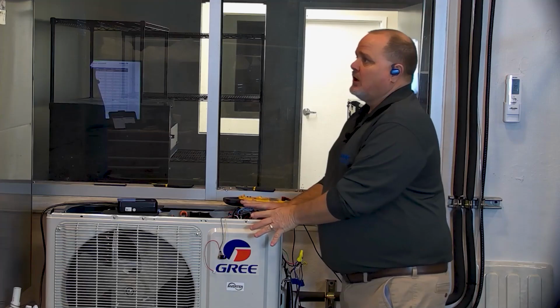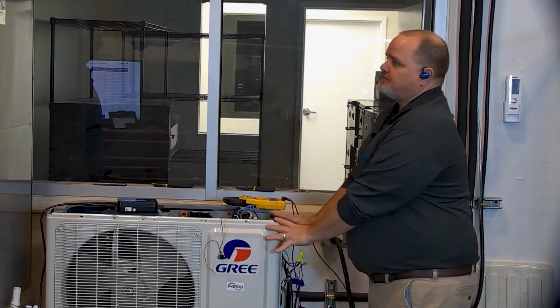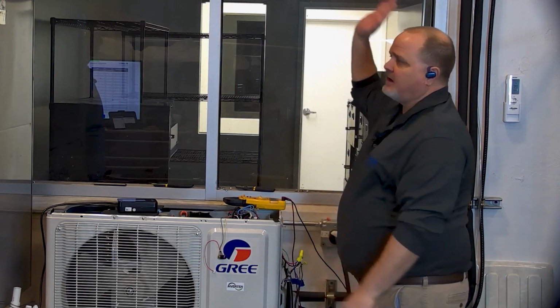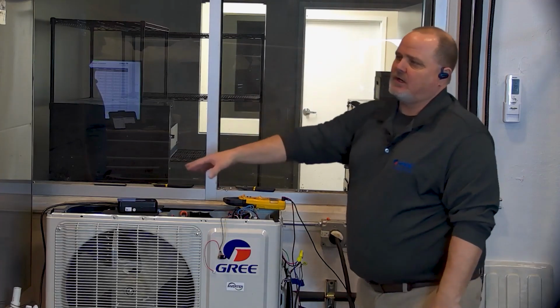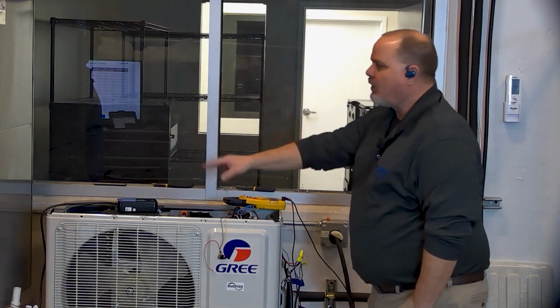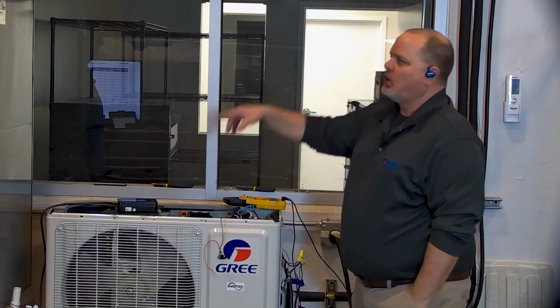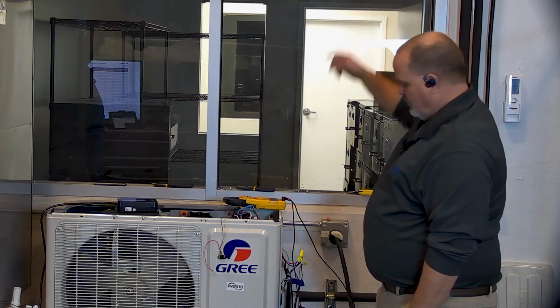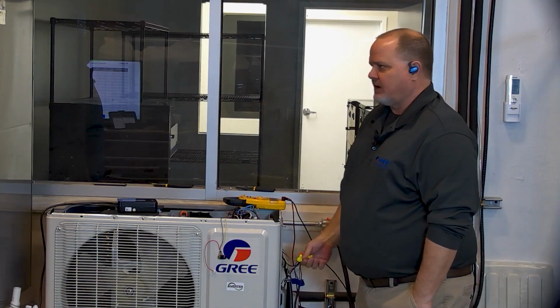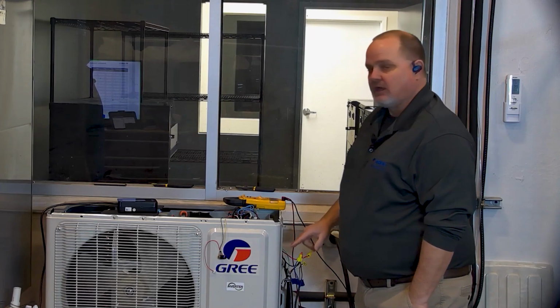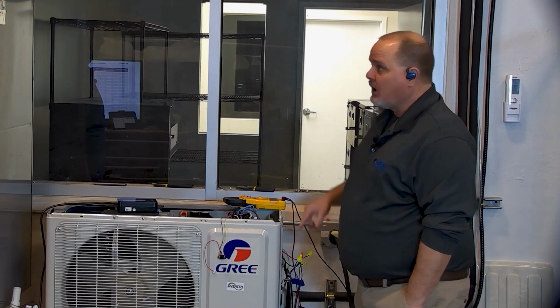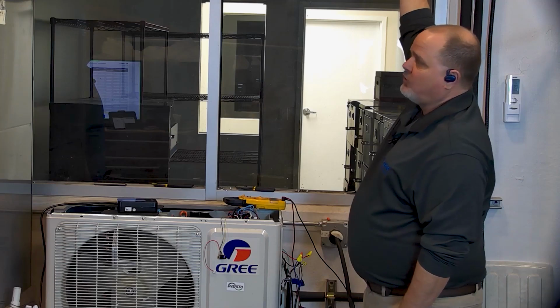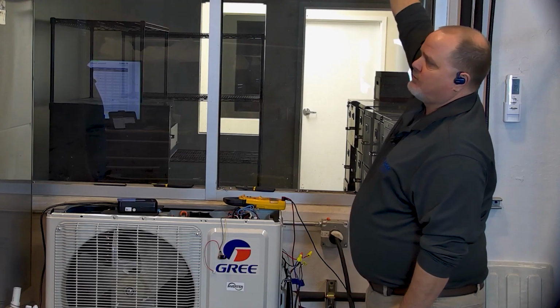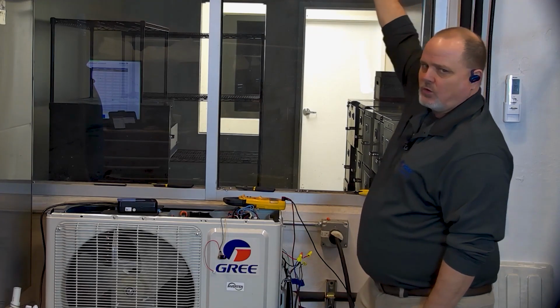So back to what I was saying. If I can't detect that indoor unit by simulating it with the service tool, I now need to take that service tool inside. You can leave that 2-wire disconnected off the outdoor machine, it doesn't matter. You need to leave 1 and 3 hooked up for power. You need to go inside, pull that 2-wire off, and hook up your service tool to 1, 2, and 3 indoors.